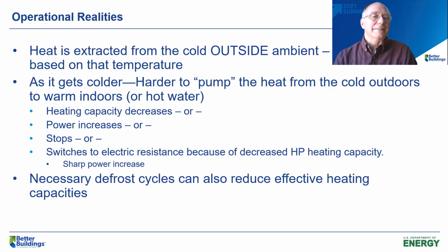The other part is that often some of this equipment will switch to electric resistance because of that decreased heating capacity, and then you've got a sharp power increase. So you need the electrical infrastructure for that, and you end up with demand charges - those are things you need to think about.